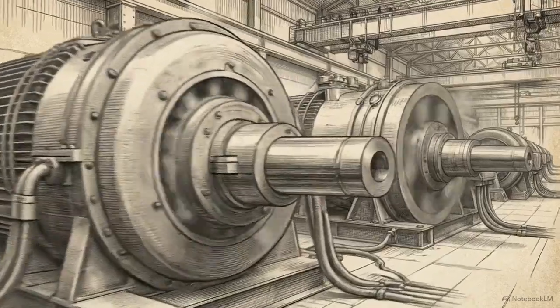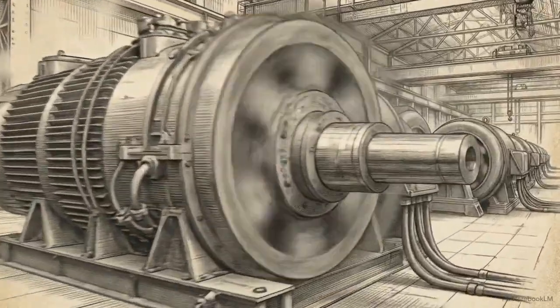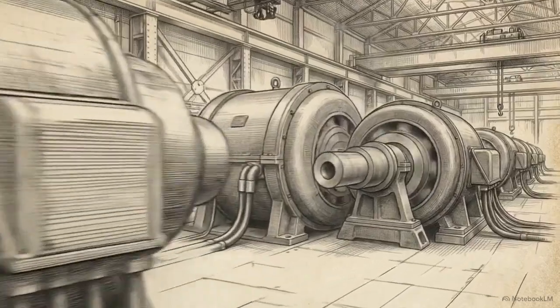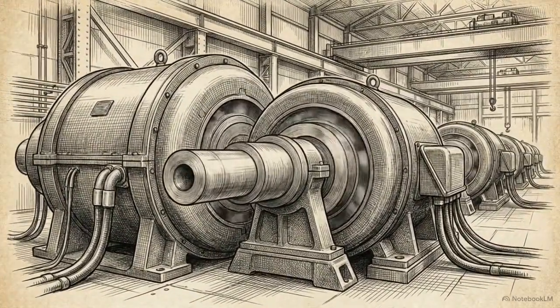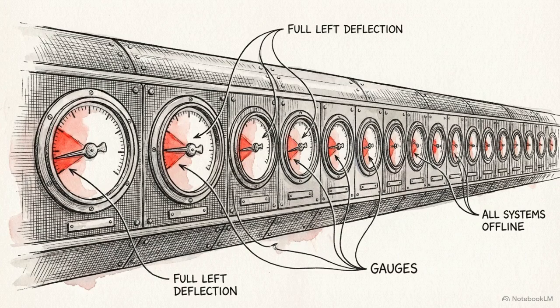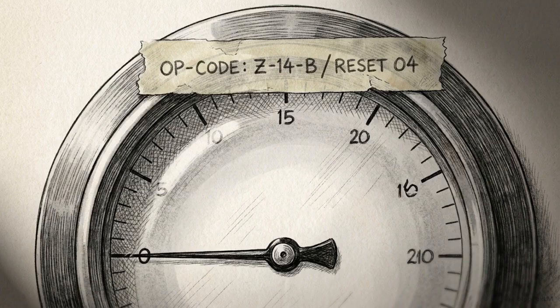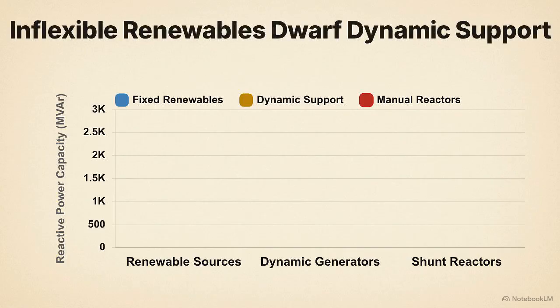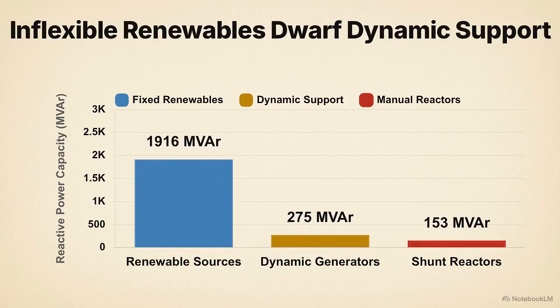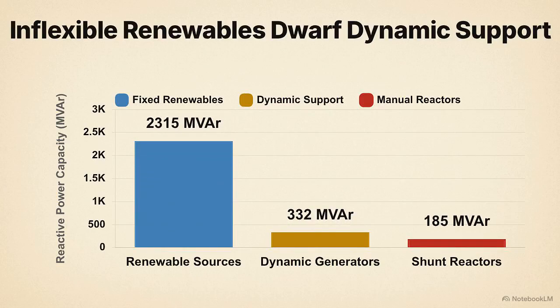To compensate for this drop in reactive absorption, conventional synchronous generators are expected to dynamically step up, providing the reactive support needed to stabilize voltage. Operational data shows that many of these conventional generators were operating well below 75% of their Q reference requirements. Q reference is the baseline reactive power target set by the transmission system operator. Looking at this capacity chart, we can contrast the massive, inflexible footprint of the fixed power factor renewable units against the much smaller capacity of the dynamic, conventional generators. The only remaining mechanisms available to control the voltage were shunt reactors.